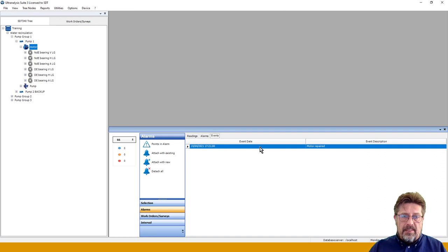At the very beginning it doesn't make much sense, I understand. But you can just imagine that if you have a certain trend, certain amount of data monitoring this point, and then one day the numbers are completely different and you have no idea why, because nobody told you that while you were on vacation we replaced the bearing of that motor, we aligned everything, we balanced the fan, and now it's a completely different situation. And of course your numbers are completely different and your alarms are not really accurate anymore. They don't work anymore for this new condition.